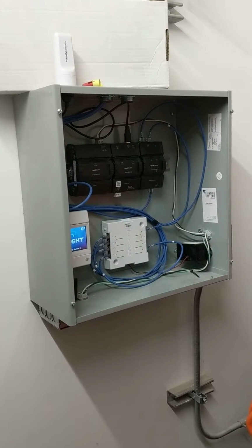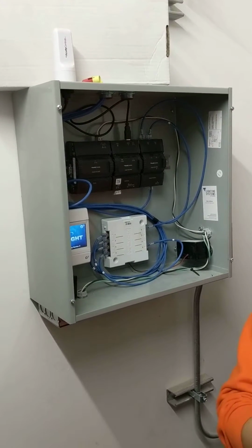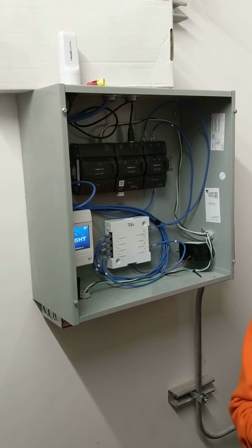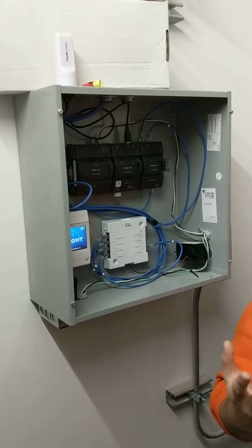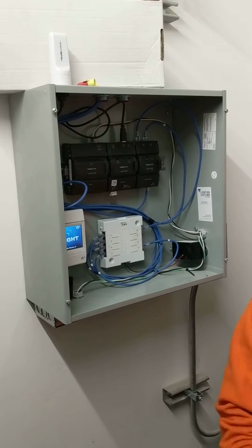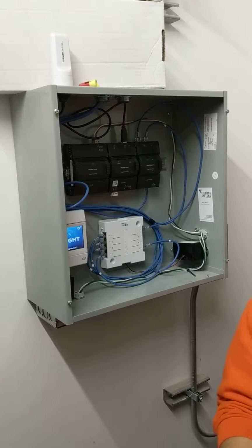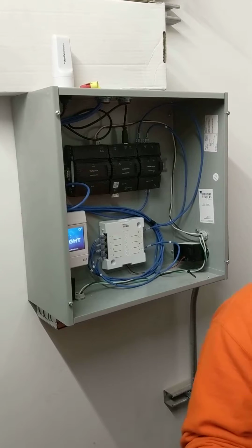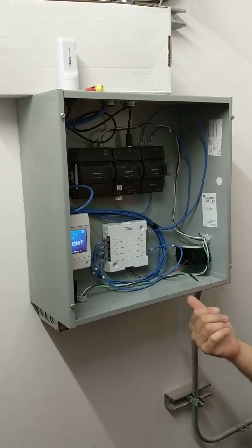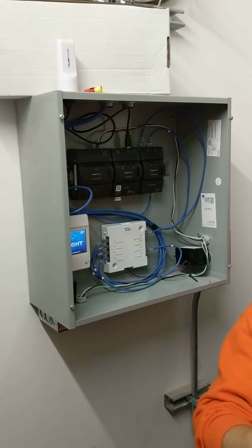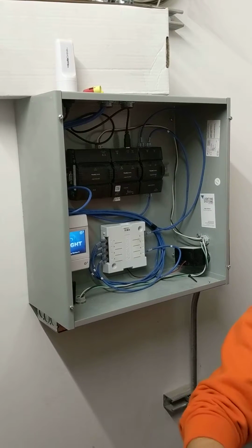There's a little caveat to that. If it times out and the lights turn off, there's a 10-second window where if somebody starts waving a hand to catch motion, it will turn them back on. But after that 10-second window, they have to go to the manual wall switch. So when you walk in first thing in the morning, if you're here before the lights turn on, you have to hit the on button and they'll turn on. We can also have it overriding on between 6:30 in the morning and 7 o'clock at night.